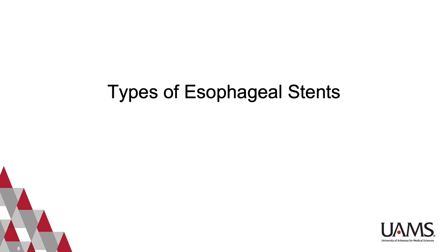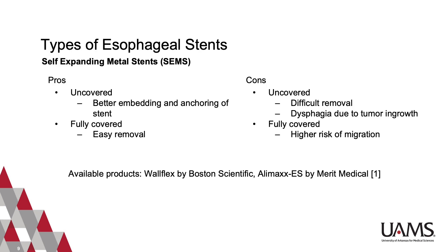We will now review the different types of stents, as well as some of the advantages and disadvantages of their use. We will begin with self-expanding metal stents, which are most often made of nitinol, an alloy of nickel and titanium. This material provides superelasticity and shape memory, expands at body temperature to fit the morphology of the lesion, and is also resistant to corrosion and hypoallergenic.